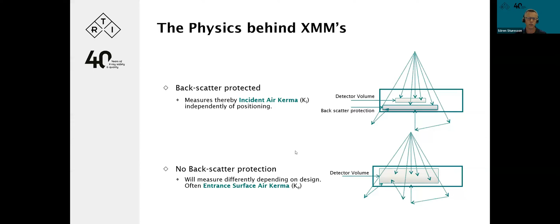Apart from backscatter, we can also look at design factors and call it front scatter. For example, in mammography, where you use the compression paddle. The compression paddle will contribute to scatter, and different detectors will sense that in different ways. The upper example here shows a very well collimated design, which is the case for many X-ray multimeters. Not all, it differs in design, but as you have to protect for scatter, that is done to different extents. But it also gives an opening angle towards the radiation that is relatively narrow. And by that, it will hinder front scatter. It will hinder scatter from, for example, the compression paddle to reach the detector volume.